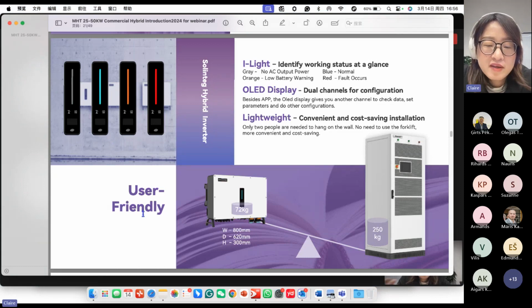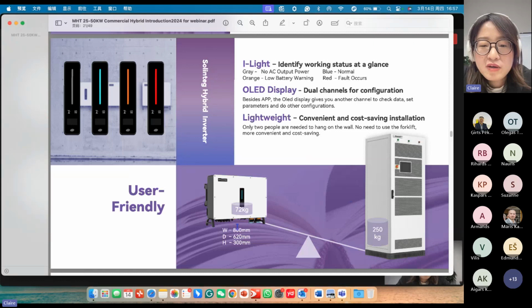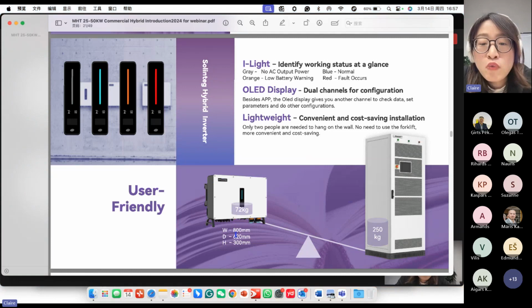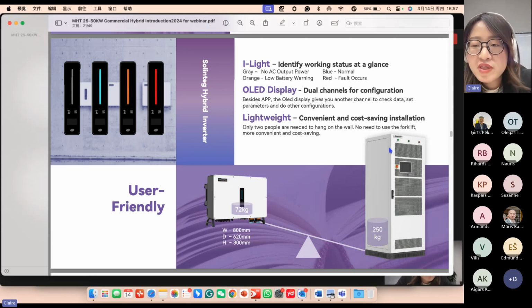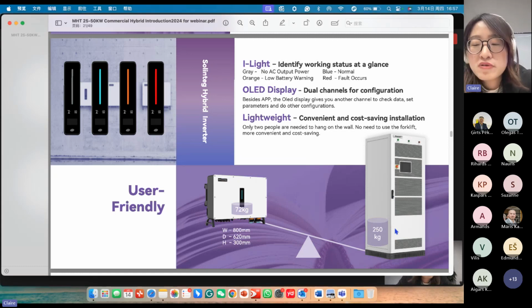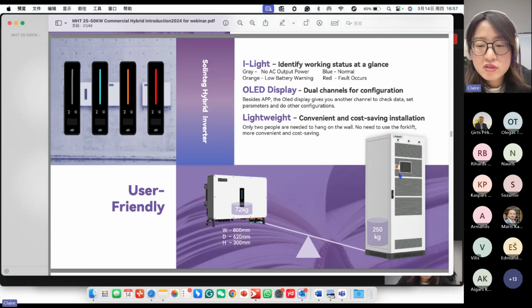Another point is that our inverter is quite compact compared with other 50 kilowatt hybrid inverters. Here you can see our inverter is a wall-mounted style inverter. It only weighs about 72 kilograms. And this one is another 50 kilowatt hybrid inverter, but it's tower style. This inverter weighs 250 kilograms. So during installation, we need a forklift to move this inverter. But for Solinteg, two or three people can hang the inverter onto the wall.